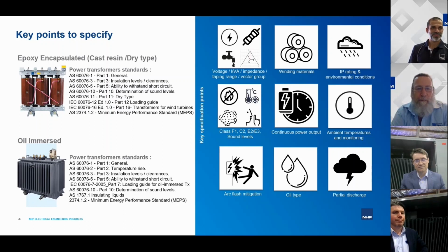Yeah, thank you, Kim. It's very interesting for me because I used to see a lot of specifications where copper was specified, a lot of consultant specifications basically saying that the winding materials had to be copper. I used to make the point that I could design you a bad transformer using copper just as easily as I could design you a good transformer using aluminium. The materials are different, but as long as your processes and your design parameters cater for those differences. So for instance, the current density for copper is higher compared to aluminium. So as long as you take those design parameters into consideration, it really doesn't matter which material you use.